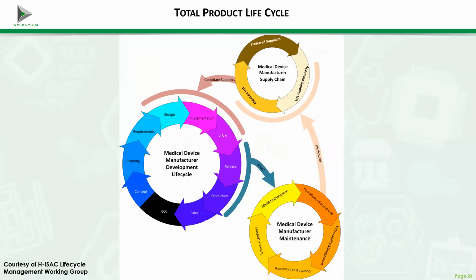Well, the large ring there that you see is pretty similar to what we've done for the last 20, 30 years and how we've developed devices. Now we're starting to add in new things, such as we release it, we create a software bill of materials, we maintain that, we do post-market surveillance, as it's called out in the post-market guidance document from the FDA, which means we're taking that software bill of materials and looking for disclosed vulnerabilities. Based upon what vulnerabilities we find after that is in the field, we do vulnerability management, coordinated disclosure.